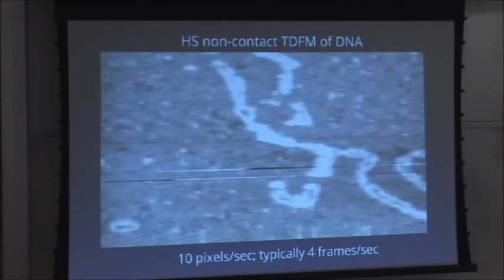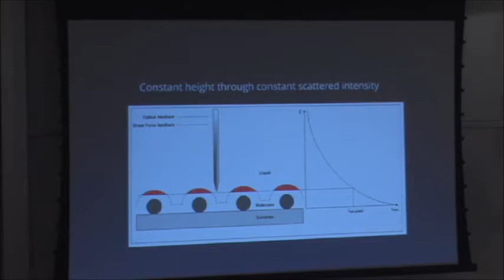There's another mode you can use it in. We've got that evanescent field, so when the probe dips into the field, it'll scatter, and the scattered intensity decays exponentially with distance, as is shown here. So as we move further away, the scattered light decreases. Yep. So this is scattered intensity. At a given level, we have a given intensity of light. That means we can fly across the surface at high speed without any feedback, except for the optical feedback. Just keep the intensity of light the same. So you're always scanning parallel to the plane. And then we can measure the mechanical properties. We can measure the mechanical interaction between the probe and the sample. Scan really fast and just see what the coupling is to the sample.